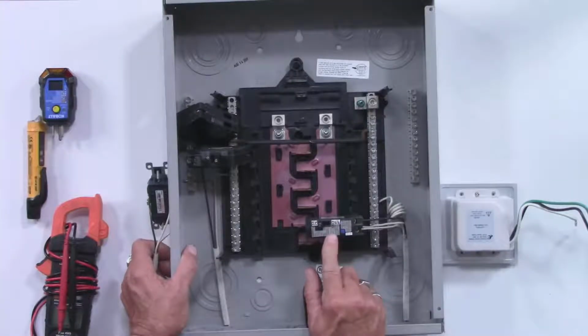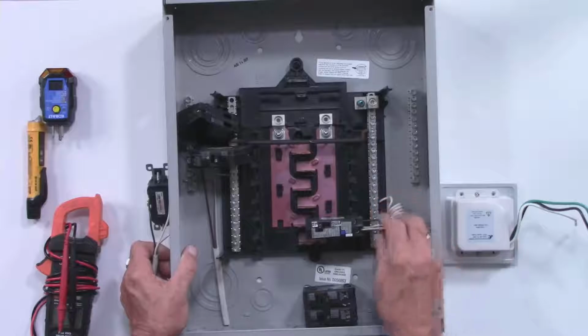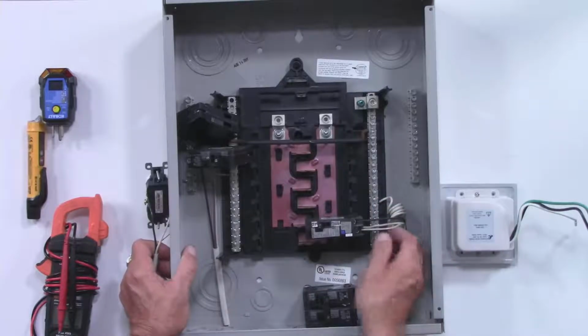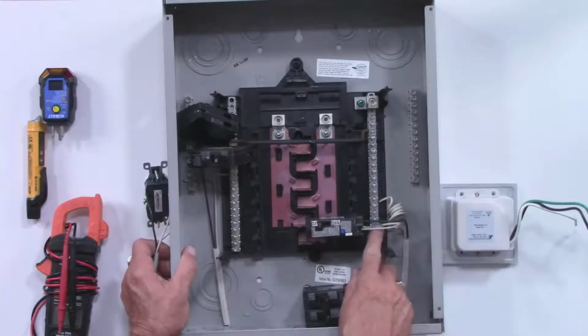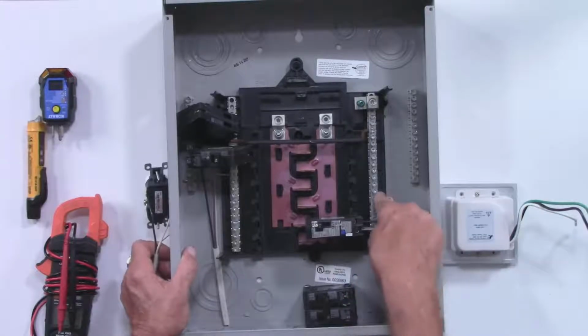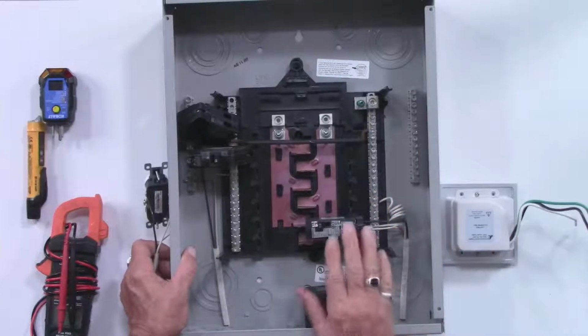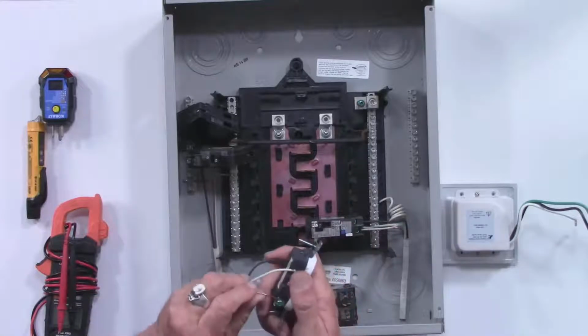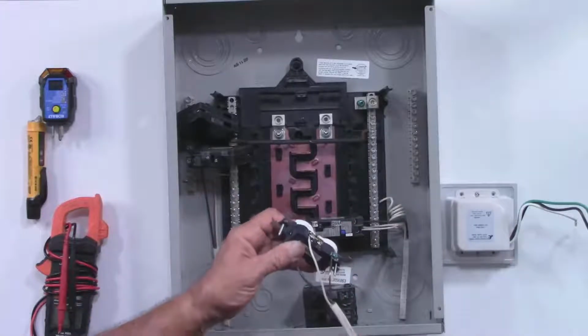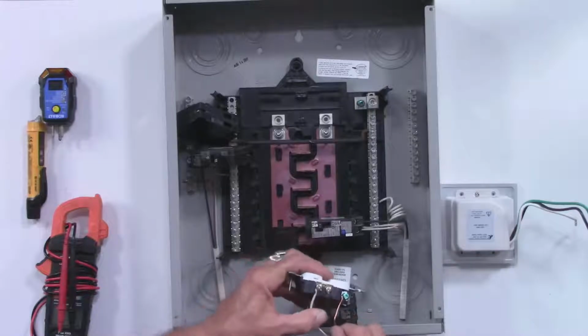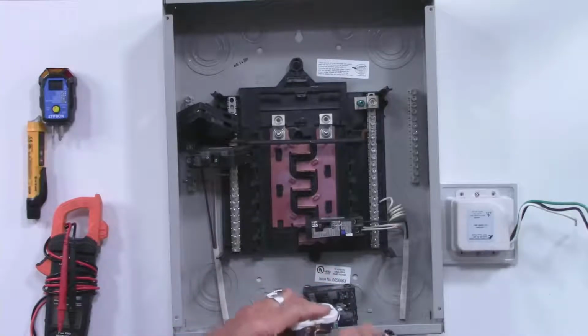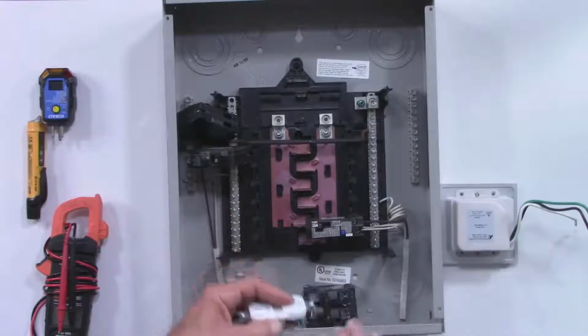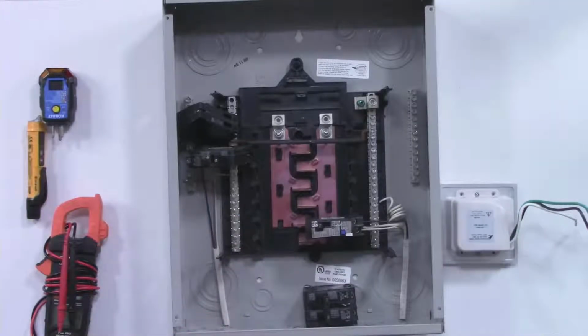This is an arc fault. As you see, the neutrals actually go into the breaker itself, and the breaker has its own neutral that goes to the neutral bar. There's a lot of different things that can trigger it. A lot of times people will pack these outlets into a box, and if the ground gets too close to the neutral, the arc fault trips and won't reset, even though it's not heavily arcing. There's enough of a change in the ground potential to trigger it. That's the whole purpose of arc faults.